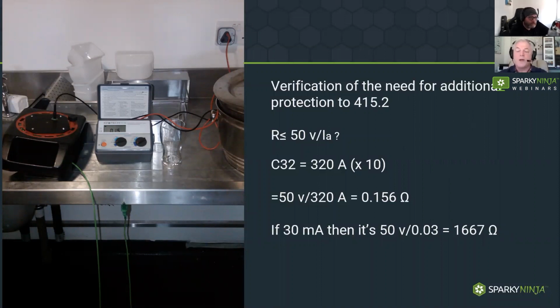But then you also get tables which have got no connection, so they aren't an extraneous conductive part. So whether they are or aren't, you need to do this test to check your connection, check your continuity, and do your calculation.